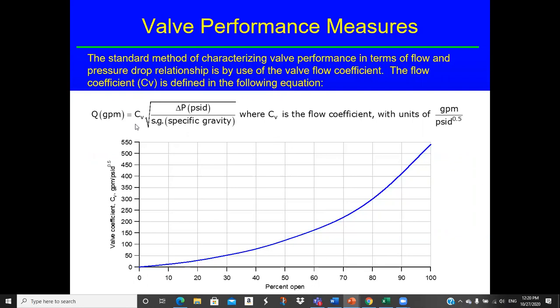And it gets used in a fairly simple equation like this. GPM, Q, the flow rate, is the CV times the square root of the pressure drop across the valve divided by the specific gravity. And so based on valve position, you can get this curve. You can read the position of the valve by looking at the handle, or there's usually a position indicator on the valve. Well, you can estimate it pretty close. Say if it was 50%, then you can read over here, it looks like the CV would be between 120 and 125. And so if you knew the flow rate, then you could use this equation to calculate the delta P for the flow. And notice the units on this, these do come with units.